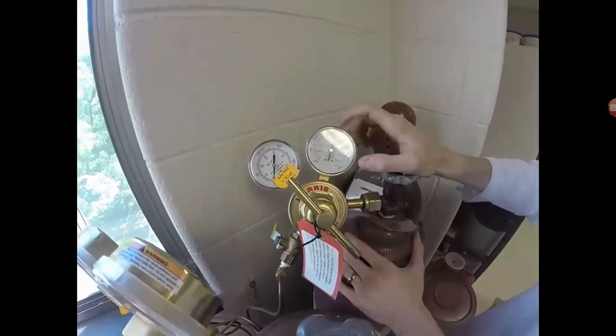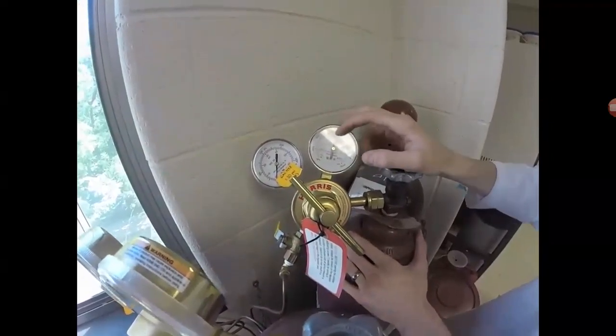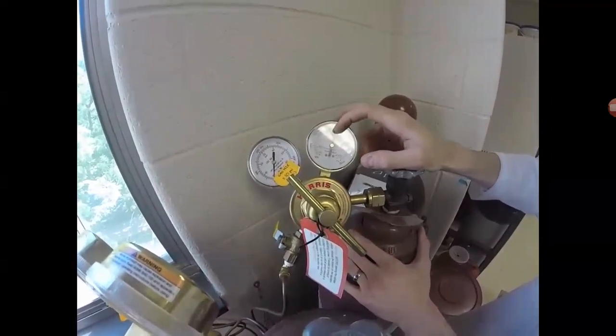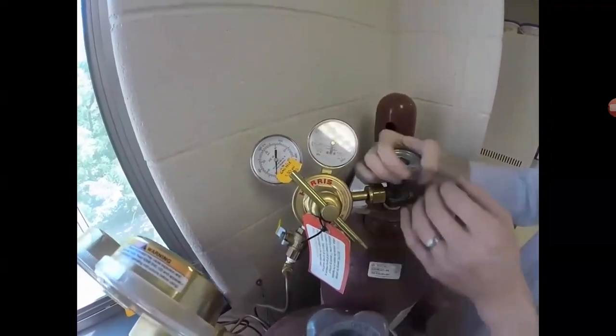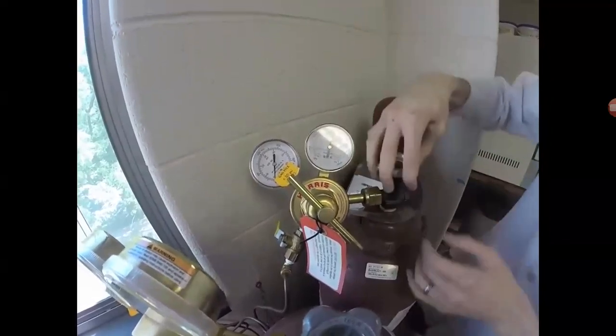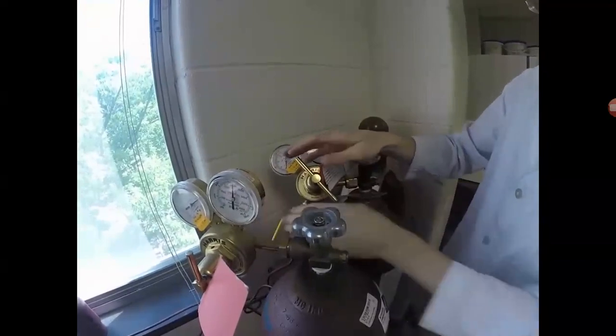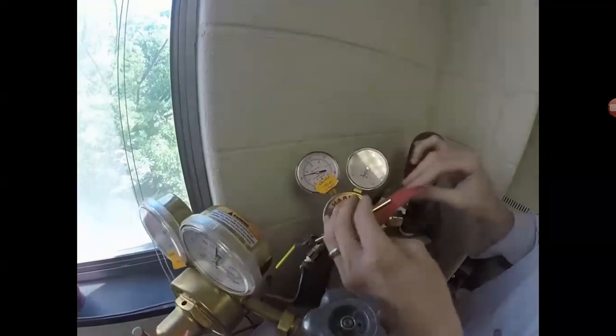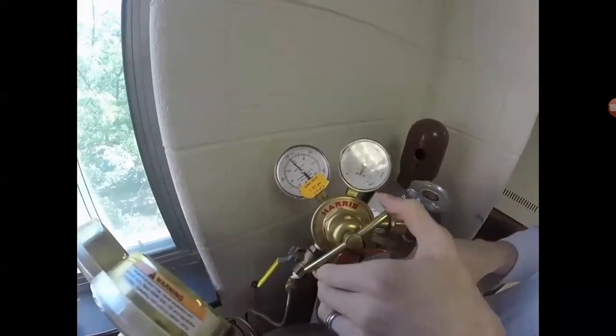And then tomorrow, or even later this afternoon, I'll check to see if the pressure is still high. If it's going down rapidly, that means that we're leaking somewhere, which is obviously problematic. Okay, so we can open that a little bit more. We can also then turn our regulator on. Okay, so you see the pressure should be rising. We're going to put it up to 30. As you can see, there's a little indicator here that says that the gas mix should be less than or equal to 30 psi. That's just indicated by the company themselves. So I leave it at that.